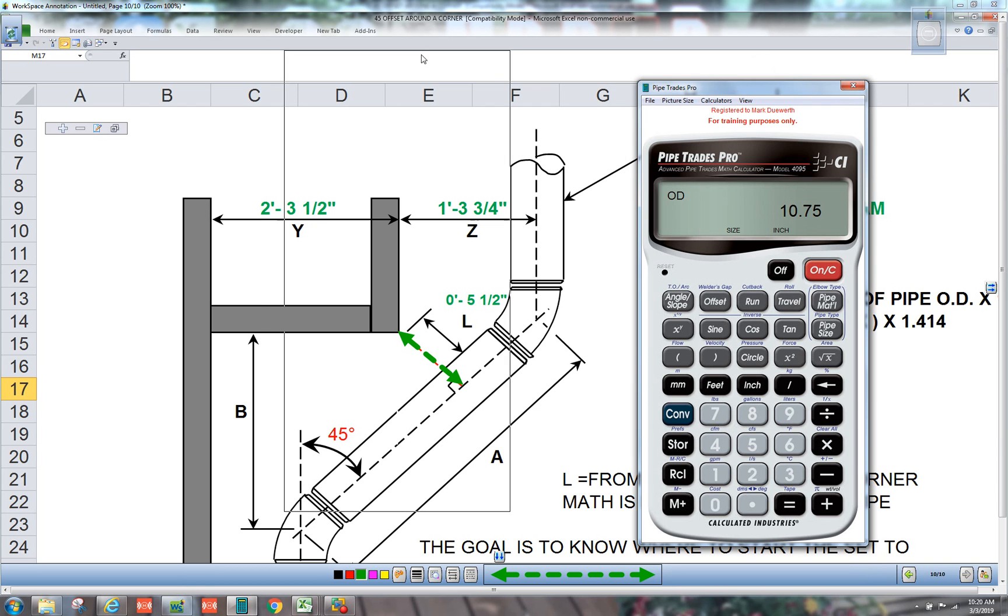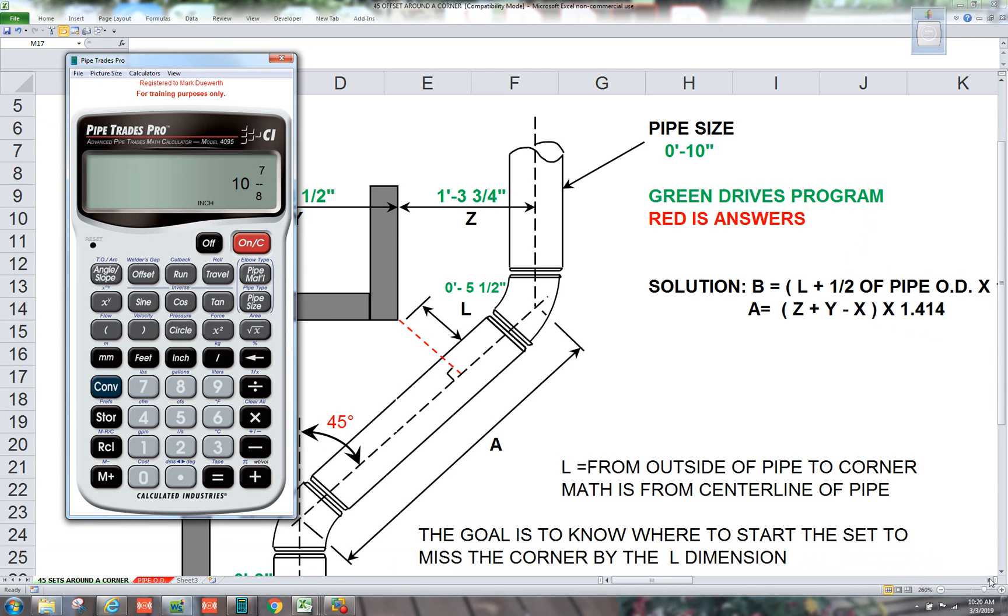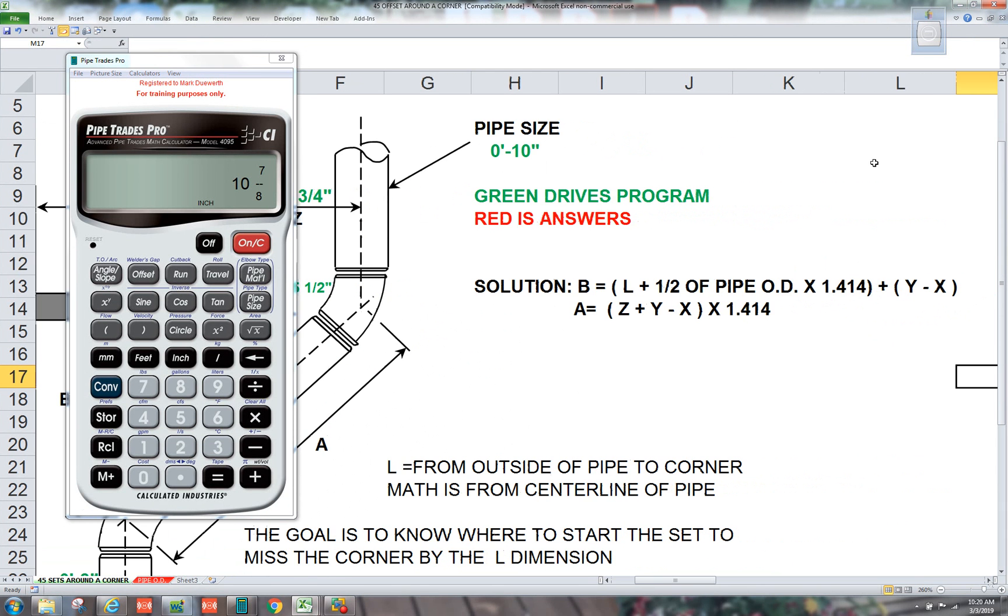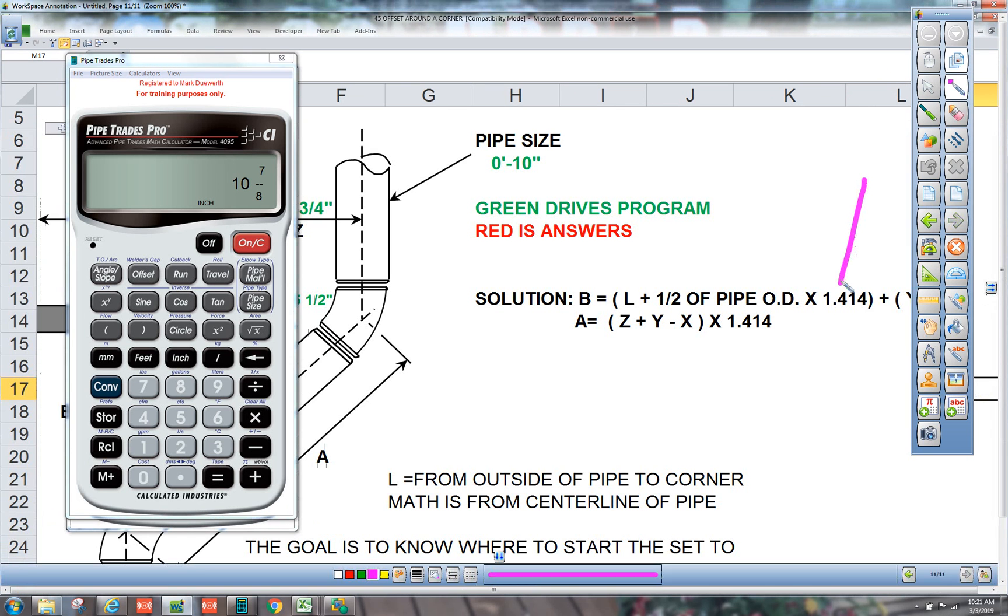So we know 10 inch pipe OD wise is 10 and 3 quarters. So let's take L, add five and a half, five inch one half. Then we have to add half of the pipe. So let's add five inch three eighths. So that's ten and seven eighths. And then at that point there, we're going to multiply it by one point four one four.